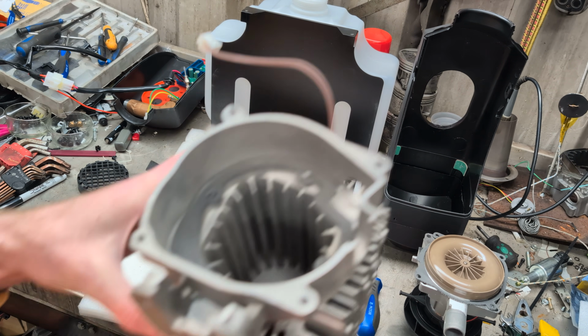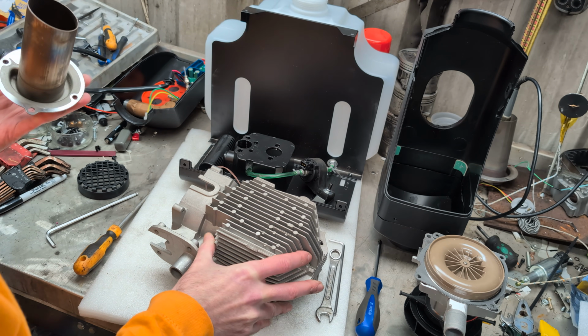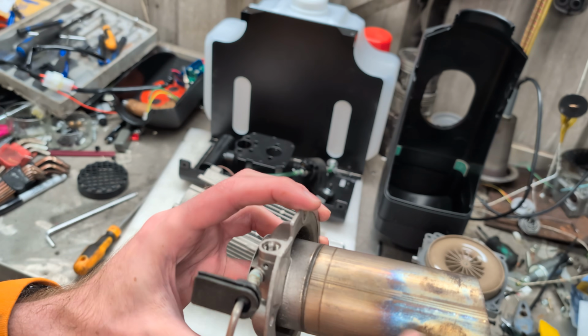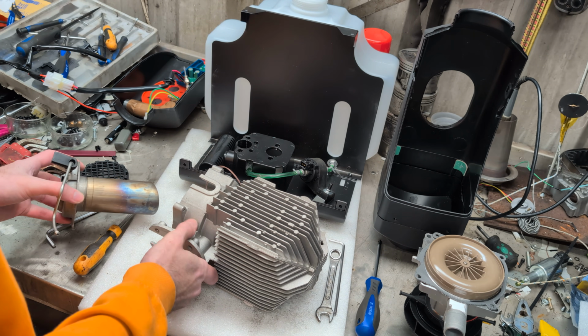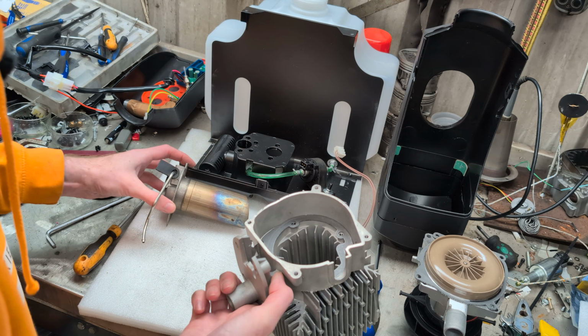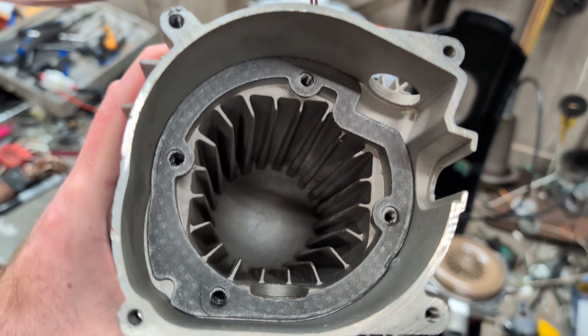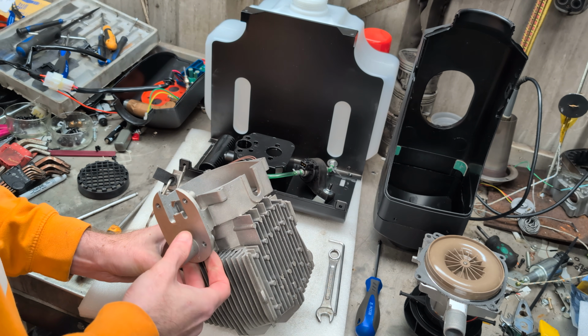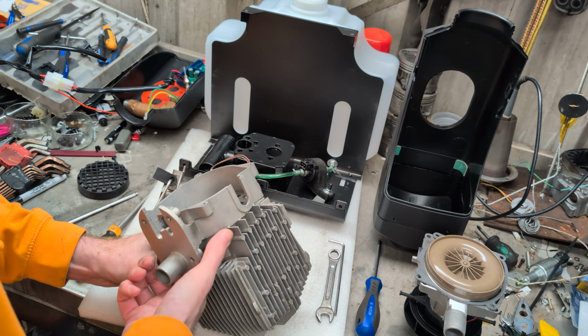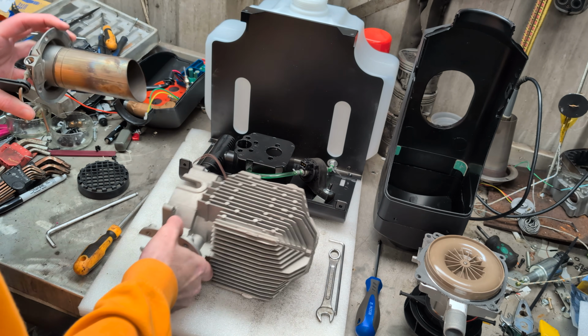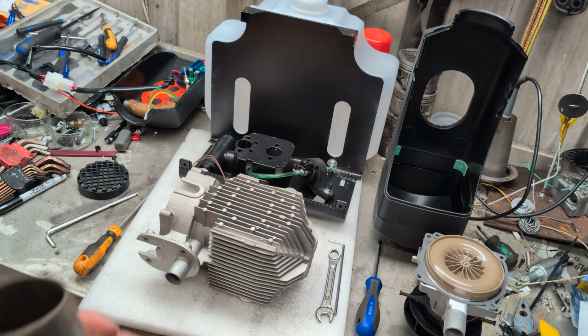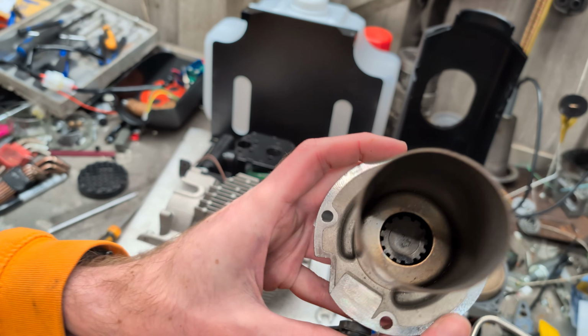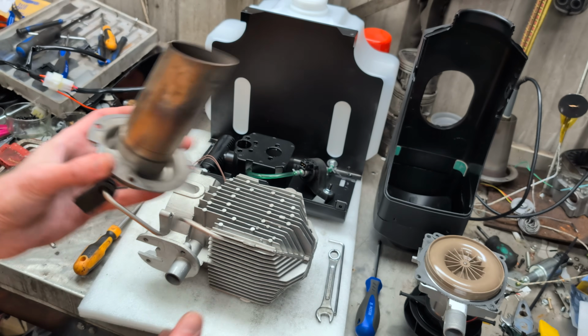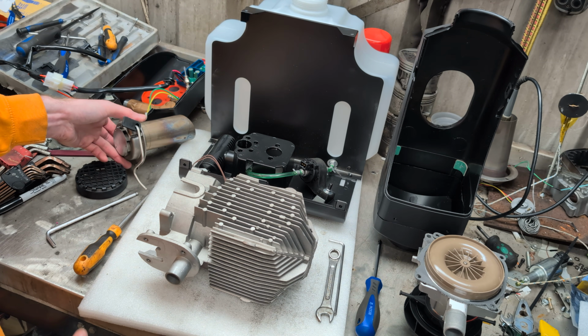Going by the colours of things, this heater has never run, so it hasn't left the factory tested. The heat exchanger looks like it's run, maybe it's been run so well there's just no carbon anywhere because it's spotless inside. Still shiny, spotless in there. But perhaps it ran briefly, or is that just discoloration from welding? Perhaps it's never run. Nah, inside the heat exchanger's got scorch marks, the inside's definitely run, not sure about the rest of the heater.